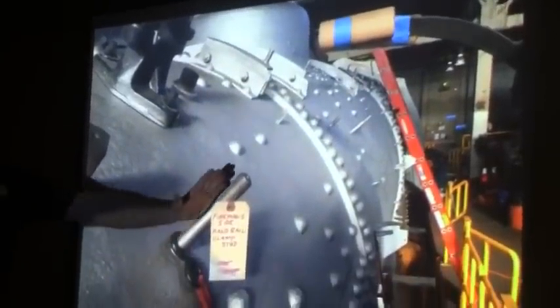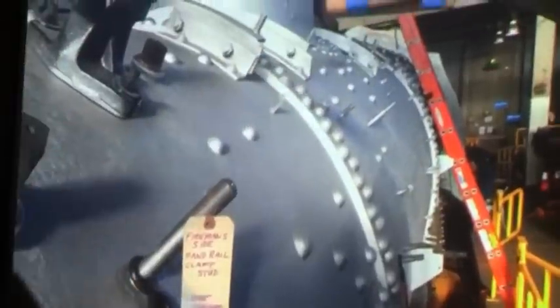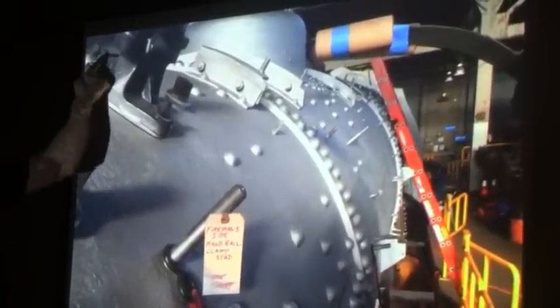We're going to jump forward just a little bit. A new stud. This is an important one because this holds the handrail. And you can see all the various studs all the way back through there. And you can see this bracket. We TIG welded a shim plate to span over the areas that were weakened, that were eroded, so that wouldn't happen again, and we removed those contact points on that bracket. And we replaced the stud. So we removed this broken stud, we cleaned the area of the boiler that had that welded bracket on there, and replaced that stud.